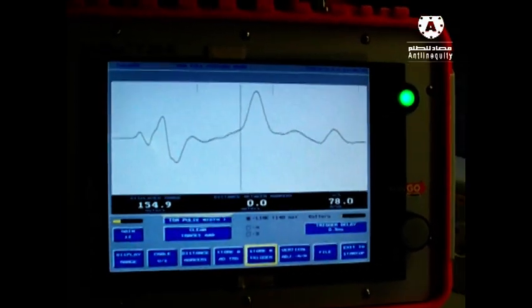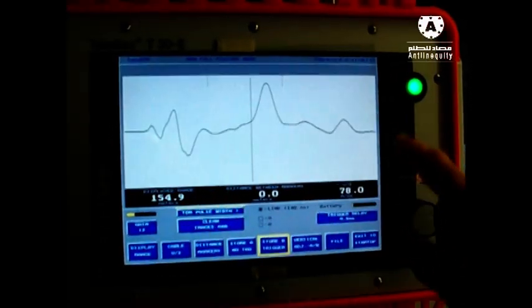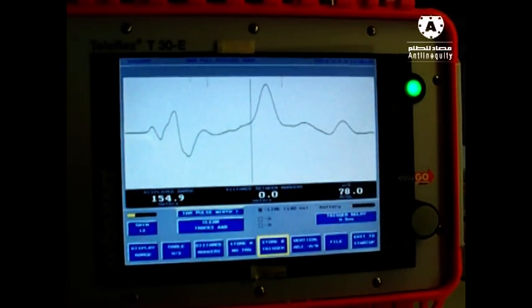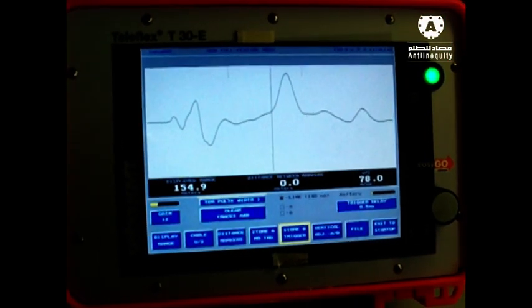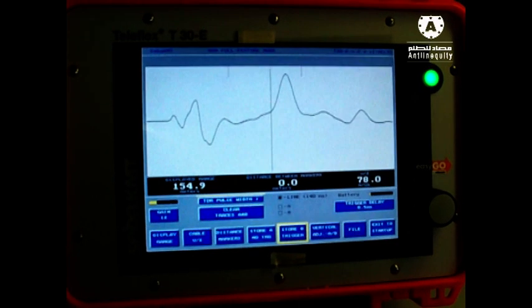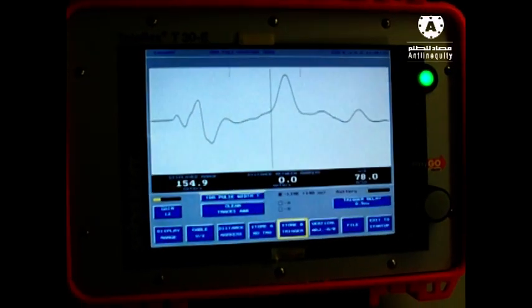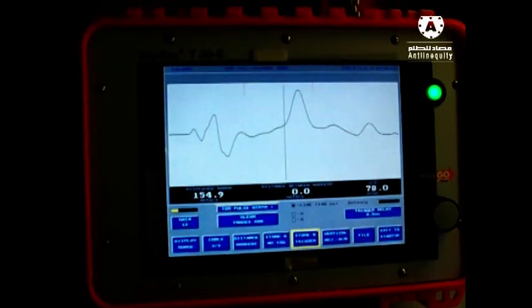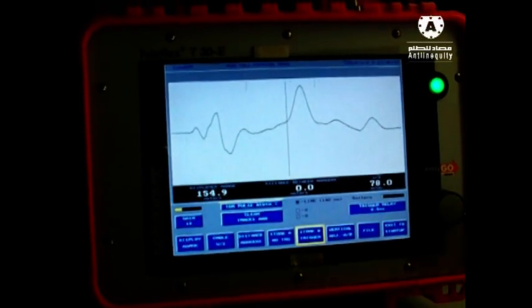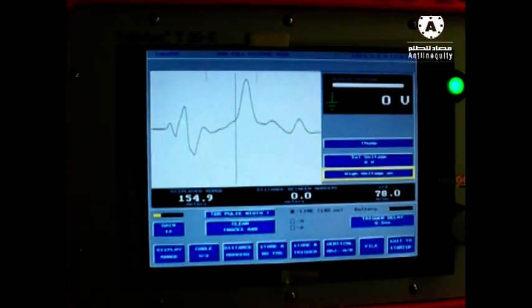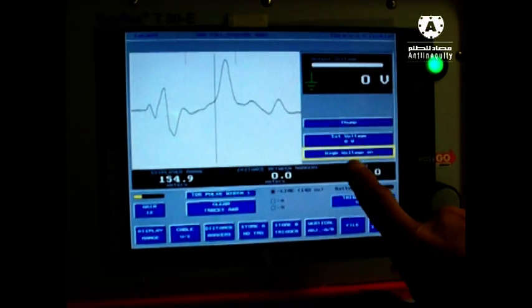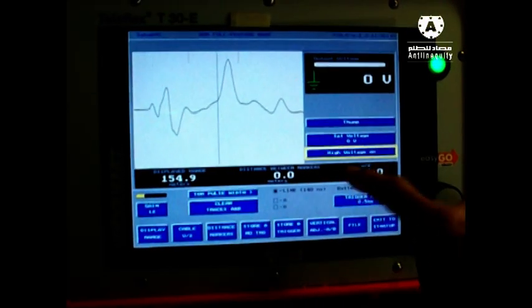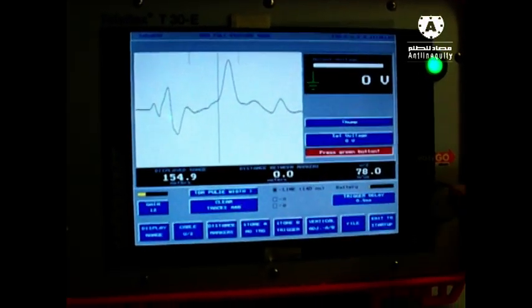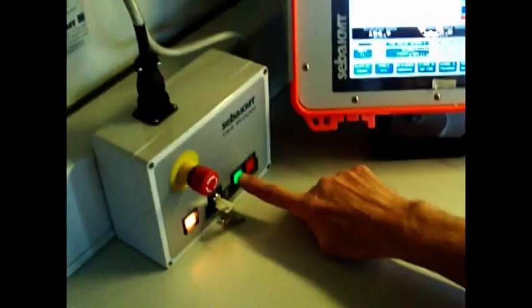That means now we will memorize the healthy picture, the reference trace, and now we will give a shock and create a flashover and a 0 ohm resistance at the fault point. Okay, let's switch it on. System is asking me now, high voltage on. I confirm once here and with the green button here.